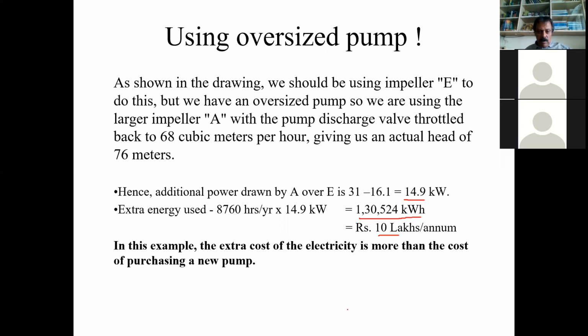So in this example, the extra cost of electricity is more than the cost of purchasing a new pump. Maybe every day you could purchase a new pump. So that's what it means. A little bit of oversizing can lead to huge losses. But this goes hidden. We don't know whether it is happening or not unless we measure the efficiencies. We find out what the power consumption is, what the hydraulic power is. All this calculation needs to be done. Then you arrive at the actual power required for a pump.